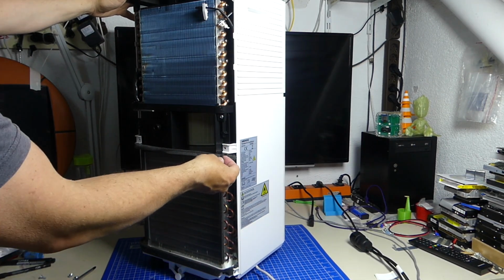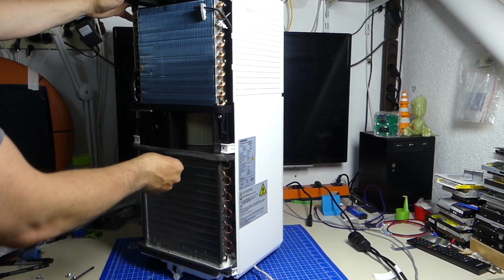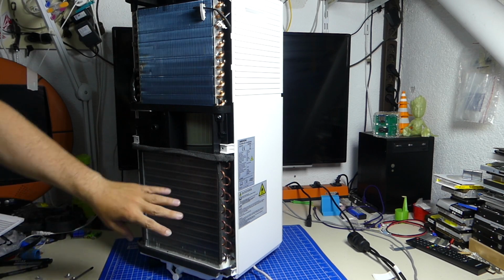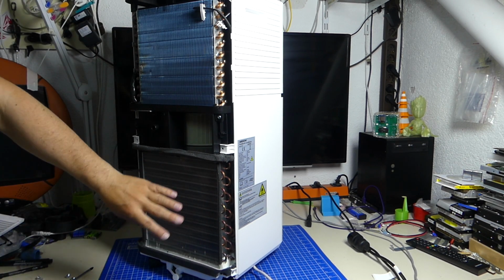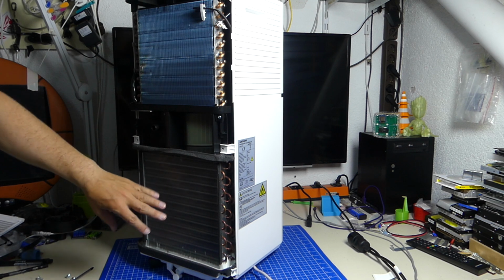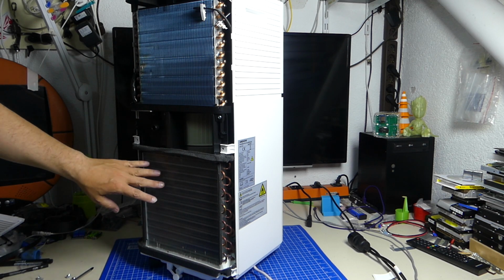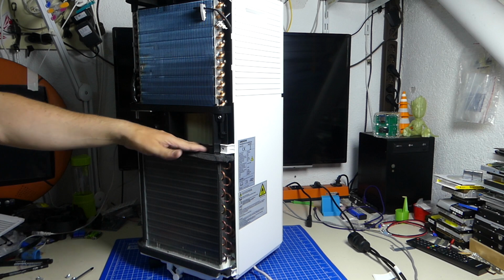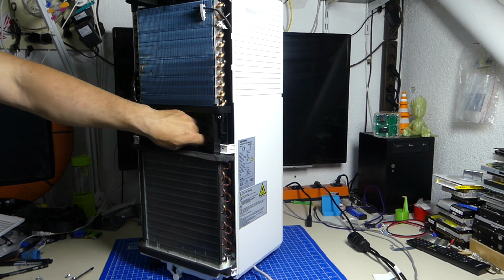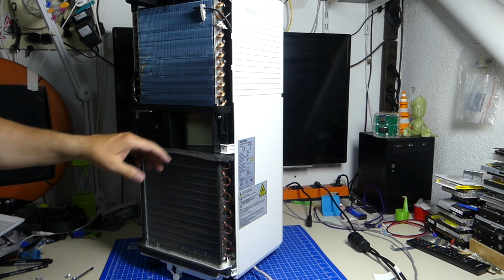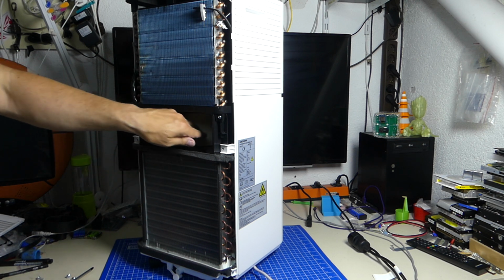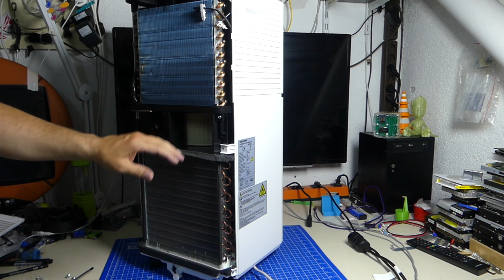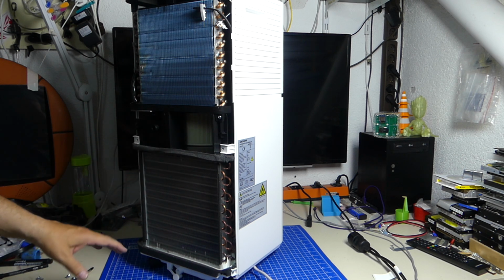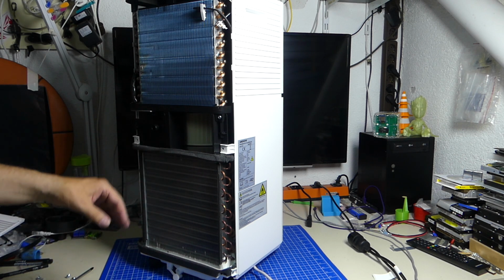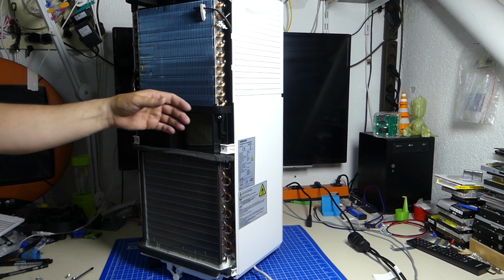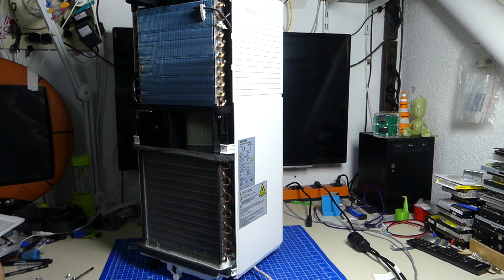Maybe let's put the back on and just turn it on for a start and block the back and see how much suction we can generate, and if we get any change of speed in the fan motor, because that would actually indicate that we're capable of pulling some sort of a vacuum, and that would show us that we're doing a good job with the separation of chambers. Let's do that.